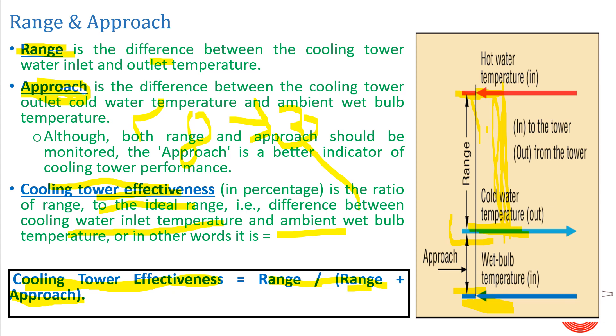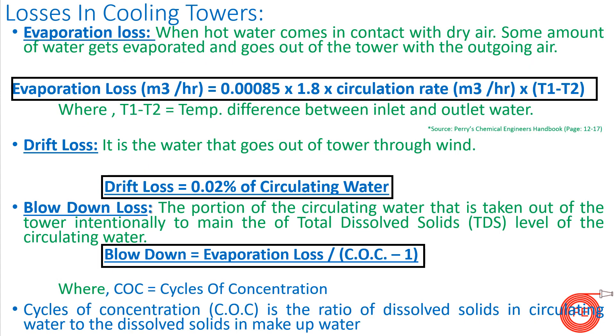Now let's see the losses in cooling towers — this is one of the most important aspects. Makeup water has to be added to the cooling tower because of losses. There are three losses: first is evaporation loss, second is drift loss, and third is blowdown loss. To maintain the water level in the system due to these losses, we have to add makeup water separately.